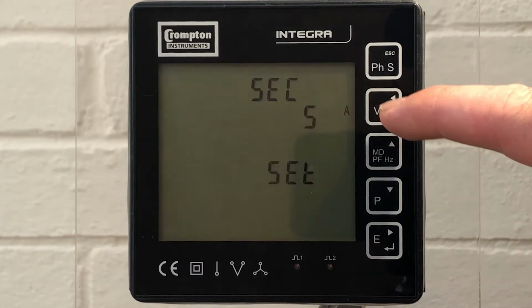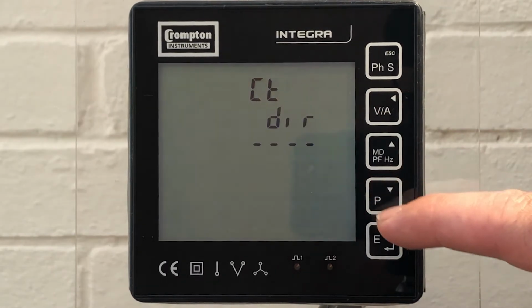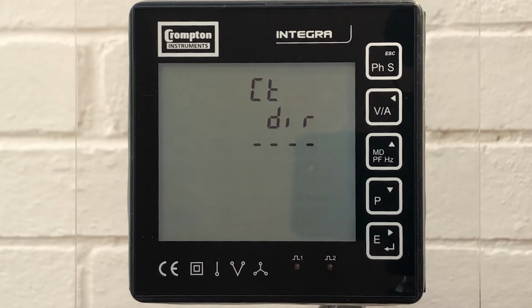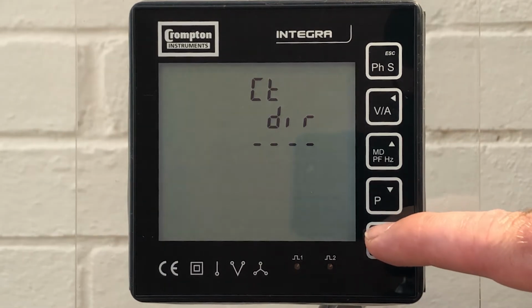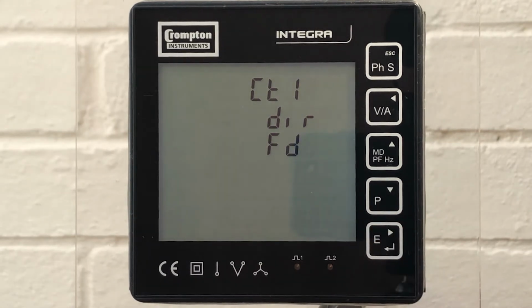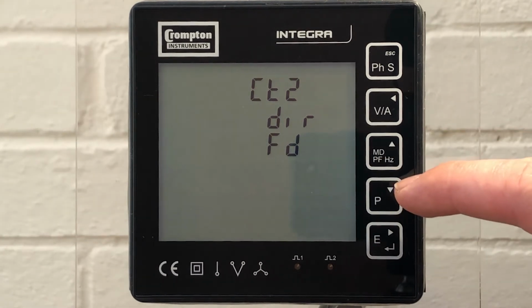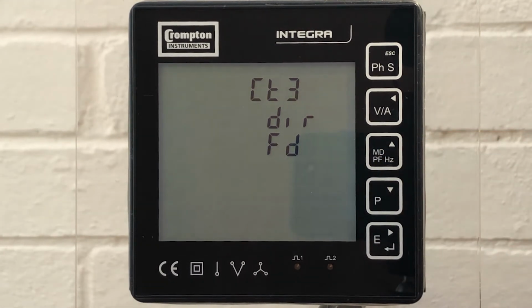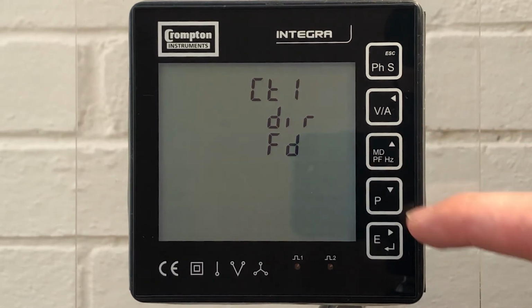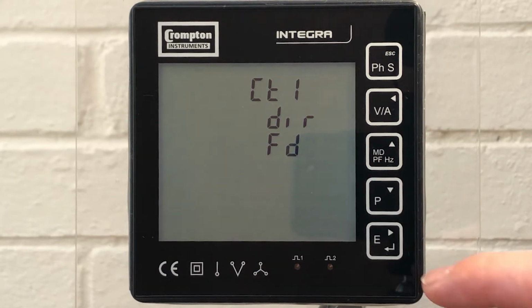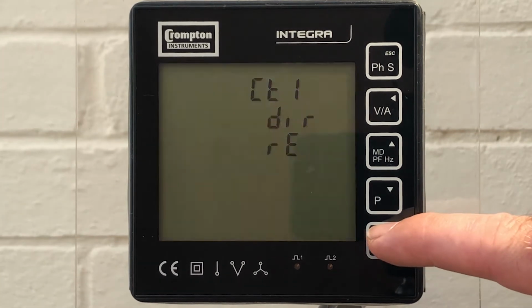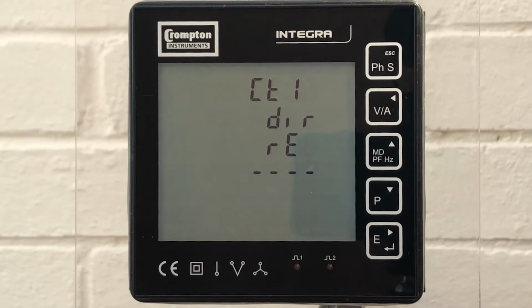displayed. A press of the VA button takes us to our next setup option, which is current transformer direction. This relates to the direction of the primary conductor, and the available options are forward or reversed, and this needs to be repeated as necessary for each CT. This is a useful feature in the event of any wiring errors, and being unable to get easily to the back of the product to correct the error, you can simply change the direction of current to reverse to correct the wiring error in the software.